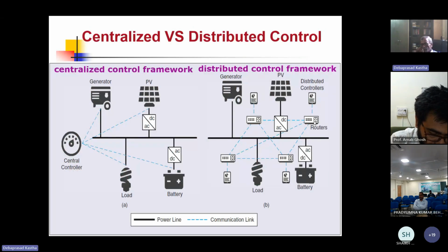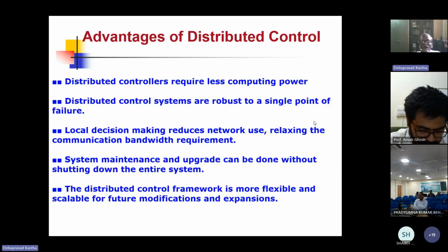Now, so far what I have talked about is what is called centralized control. It has primary control, secondary control, and tertiary control. In each case, you have a central controller. Now, that concept is slowly being replaced by another concept called the distributed control framework. The reason being, the centralized controller has several problems. Let us look at this. Distributed controllers require less computing power. If your distributed generation system or microgrid is large, your computational requirement will also be large. And the problem is, upgrading it will be a problem, because if you keep on adding newer generators and newer microgrids, then sooner or later you are going to run out of your computational resource.